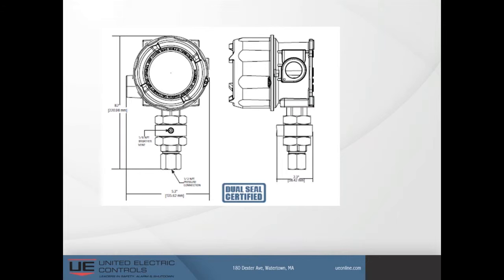The real selling value of UE's MO41 option is that this device was designed specifically to meet the dual seal ratings and the dual seal certification criteria through NFPA and NEC. The design of this product is the standard welded 316 stainless steel sensor. Should that diaphragm be compromised, you would get leakage into the intermediate chamber, which would then go out to atmosphere or could be scrubbed, and then there is a glass to metal header to keep that leakage, or that compromise, out of the enclosure.